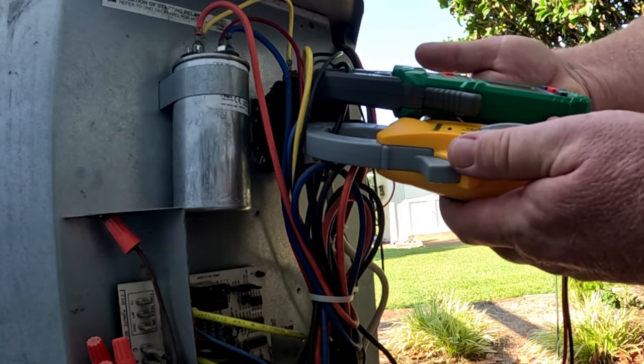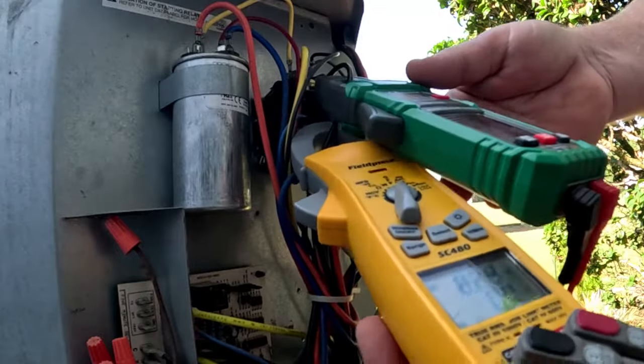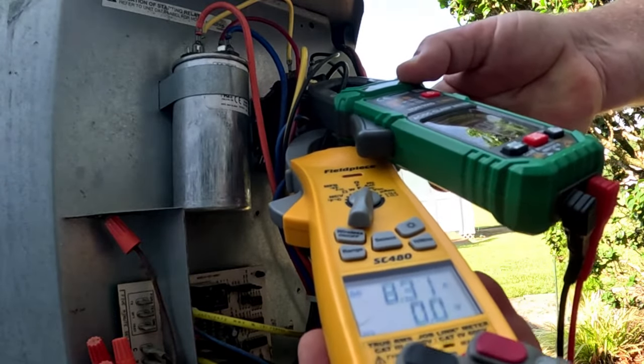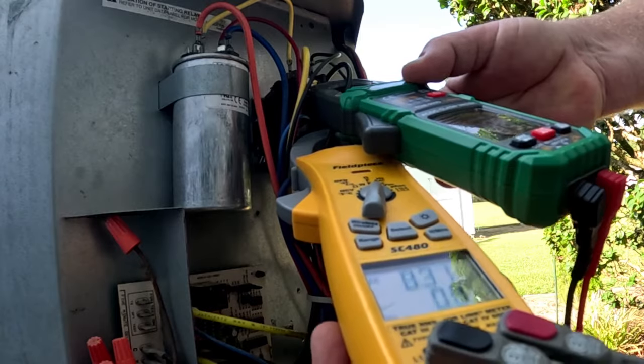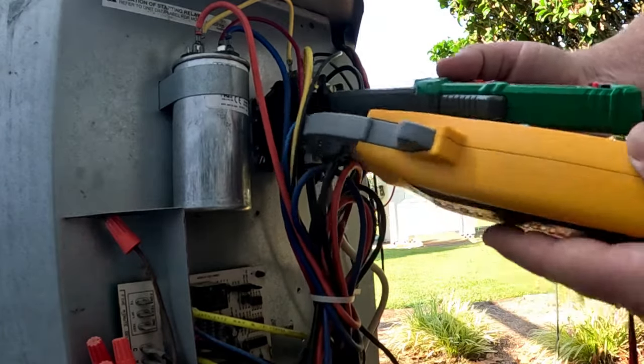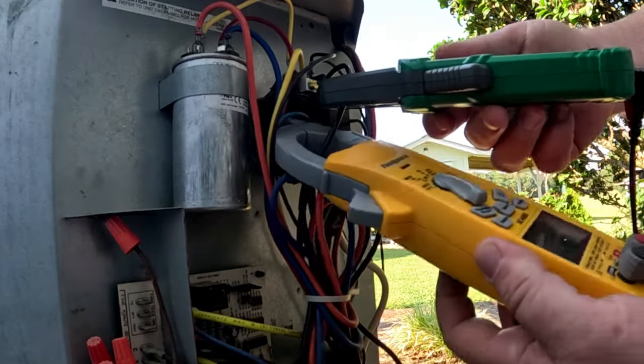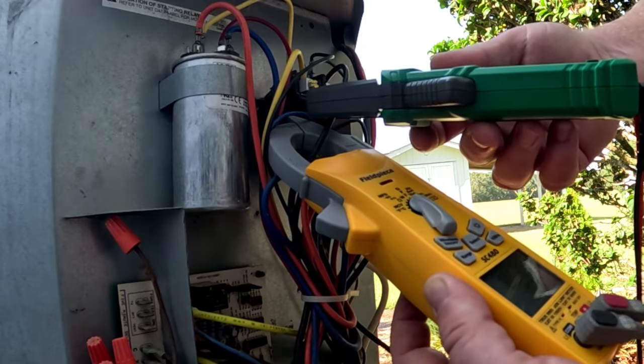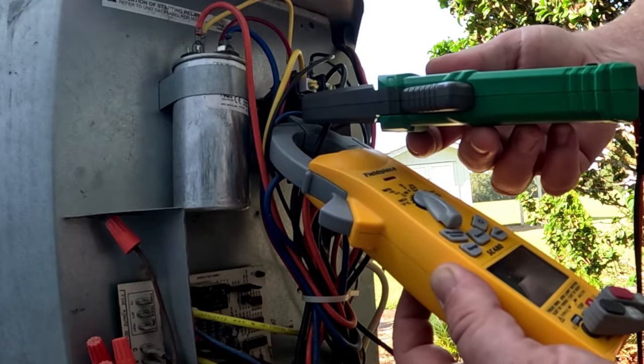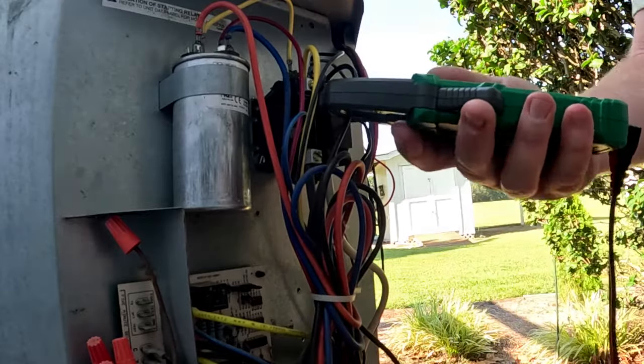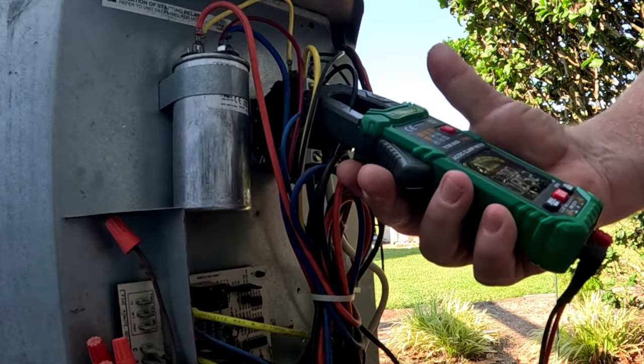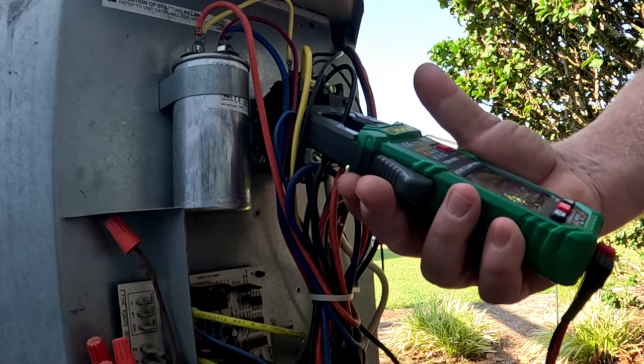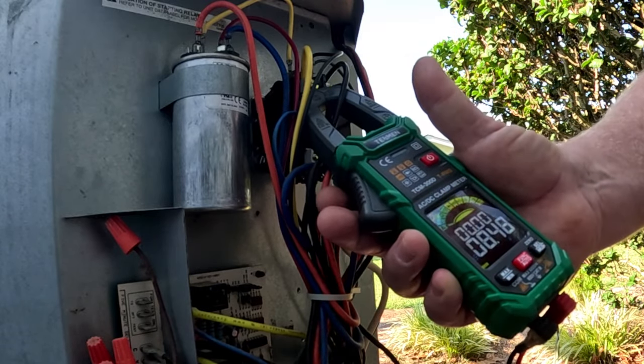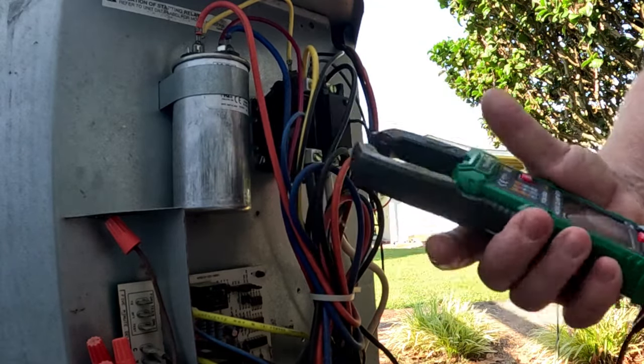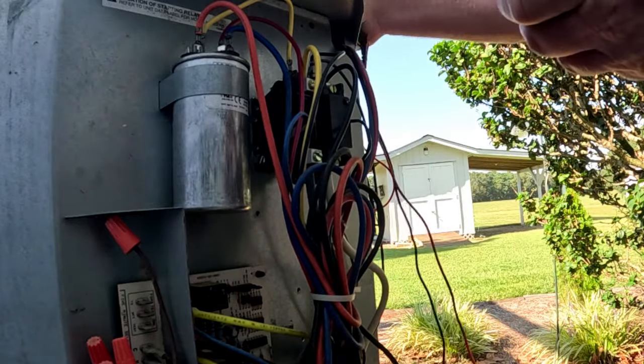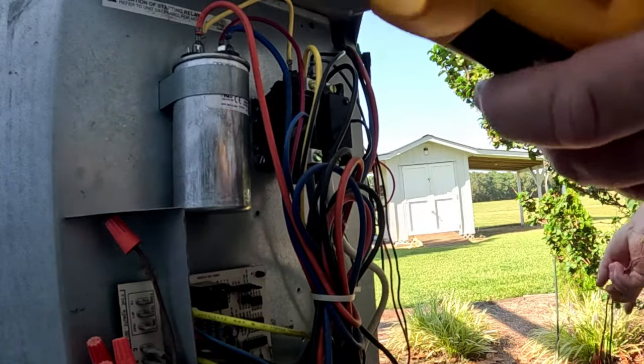Right now, on both of them, as I look at them, that one's 8.3. It depends on the angle where this wire is, so I'm getting 8.6 right there with the wire centered in the middle of my clamp on the FieldPiece, and I'm getting 8.5 on this one right there, 8.48. Pretty accurate with the amps. We'll see how it does with low voltage real quick.